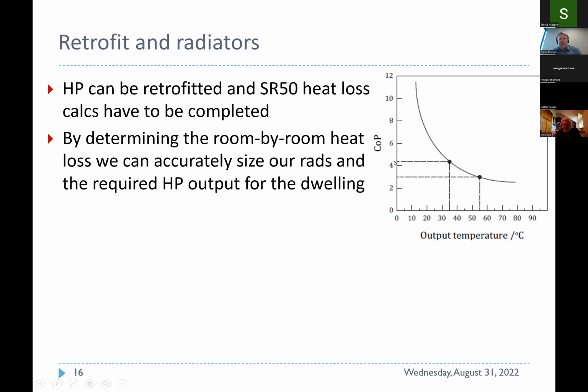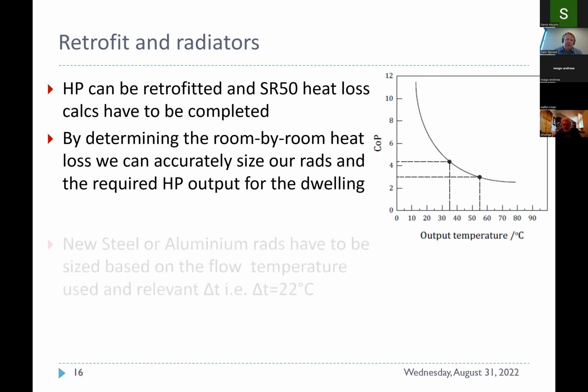Like, an SCOP of 4 means that for every unit of electricity consumed, you will generate an extra 3. So if your cost per kilowatt hour of electricity is 20 cents, if you apply that efficiency, it actually costs you 5 cents to run that on a yearly basis. Now, I don't know what's going to happen over the next few months. Unfortunately, this price is just going to go up, but it still applies the same. And in particular with gas at the moment, it is very efficient to run a heat pump, and oil as well.